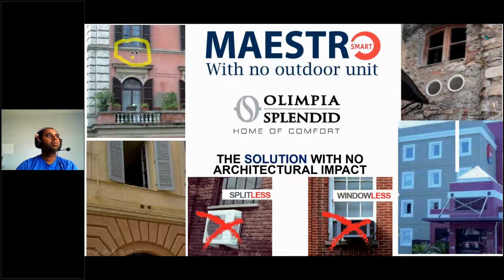But if we go over to the other side here, so upper right-hand side, you can see two grills here also installed below a window. But on the next, on the right-hand side, on the second picture, you can see a series of these grills, and each one of these apartments had one installed high on the wall. So the point here is you can install this equipment either 4 inches from the ceiling or 4 inches from the floor or anywhere in between on an outside wall. So we're going to talk about that, but it must be installed on a wall that communicates with the outside.